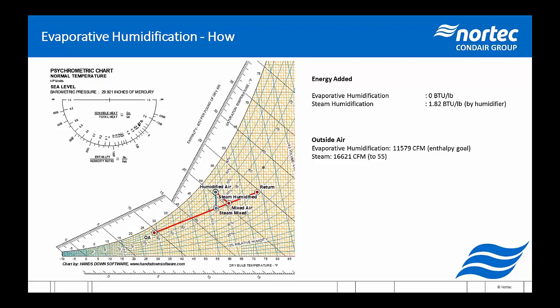When in economizer mode, you're typically skipping your energy wheel. So that's the situation we're looking at here, where instead of bringing in 100 or 60% outside air, we bring in 50% outside air or something like that in order to bring us back to our humidification set point and temperature set point without adding energy.